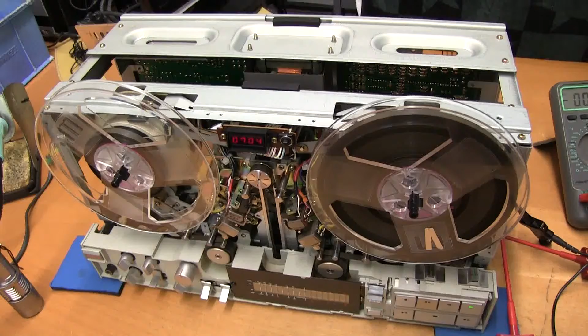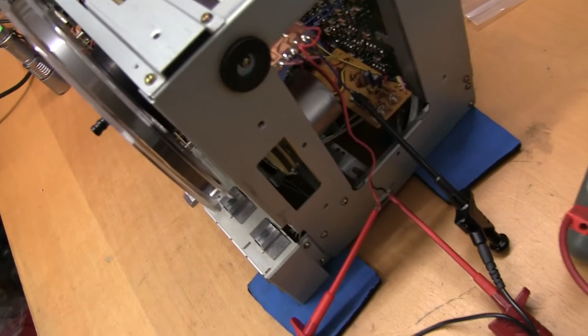Just trying to sort out this slow wind problem on these GX-77 recorders. I've got an ammeter in series with the spool motor and a voltmeter measuring the voltage to it, which should be about 16 volts on spooling. The ammeter is set to the 10 amp scale at the moment, but when the spool is heavy and we try to spool it...